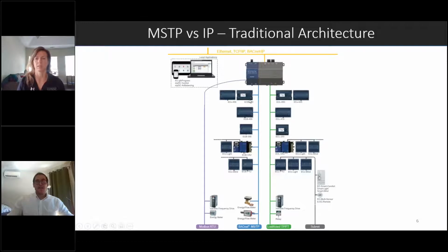We have an MSTP link going back to this controller. We're also showing LON controllers all being networked back to this, even Modbus. Ultimately at the top, it communicates out IP to your local area network and facility staff front end computer. But what's happening here is the speed of communication and the security and everything is kind of down to what's happening at these unit level controllers. So some of those IT security practices we're going to talk about are a little bit harder to implement over these serial communications that we have here.